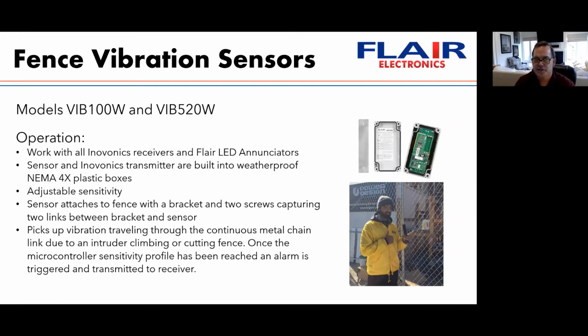The sensors attach to the fence with a bracket and 2 screws, capturing 2 of the chain links between the bracket and the sensor. The vibration sensors pick up vibration traveling through the continuous metal chain link due to an intruder climbing or cutting the fence. Once the microcontroller's sensitivity profile on the sensor has been reached, an alarm is triggered and transmitted to the receiver.